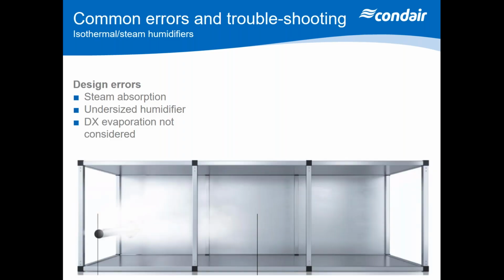So now I'm just going to quickly touch on the common errors in troubleshooting. We see this quite often in commissioning over the years, in that with the steam absorption, we'll see a sensor maybe put maybe a meter away from the lines. Now, what's going to happen, as you can still see water vapor coming off here. So if this is, say, a meter at this point, you're going to be coming off 95% here.